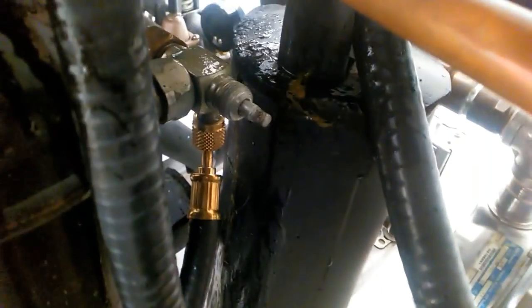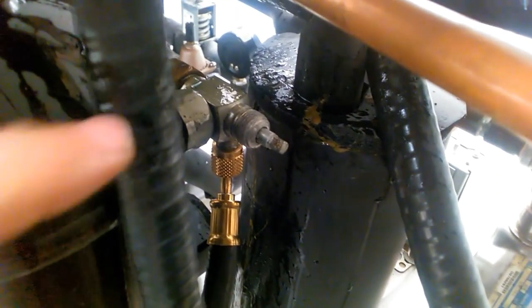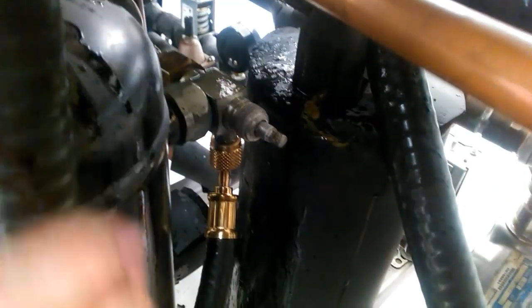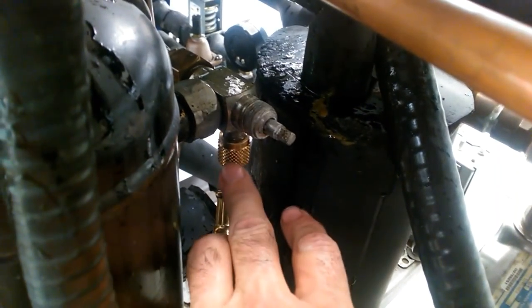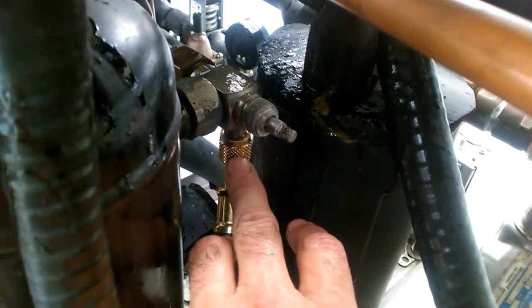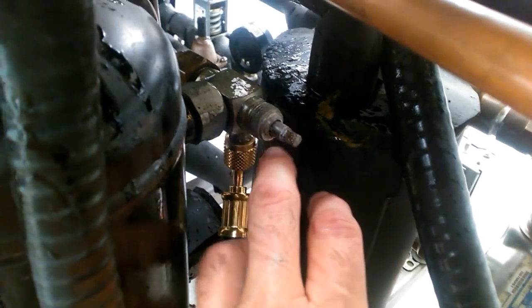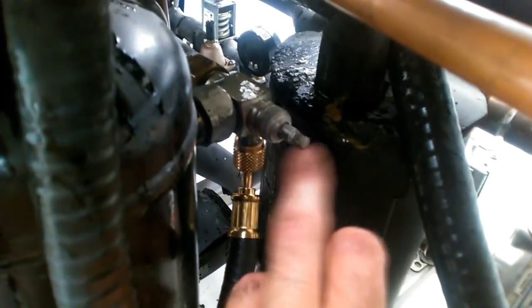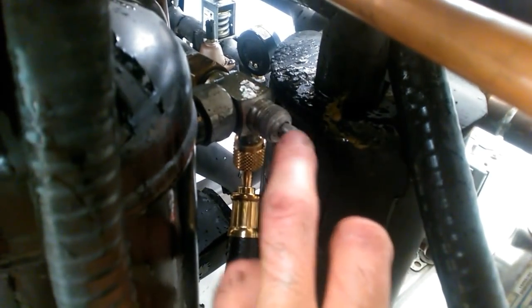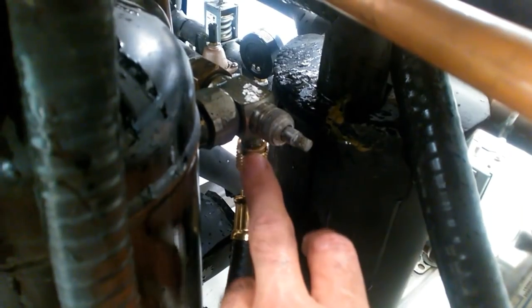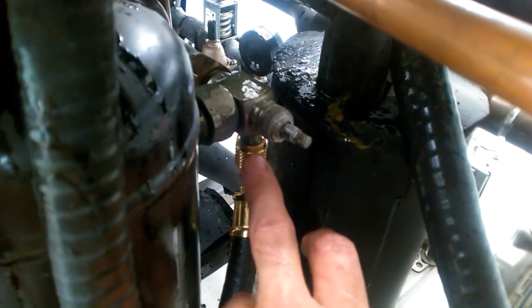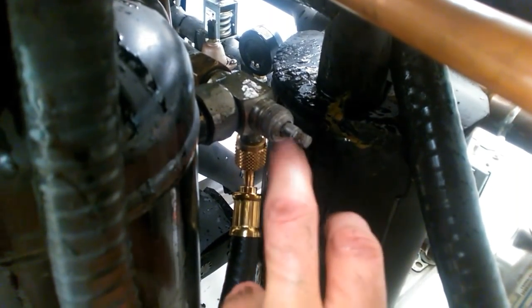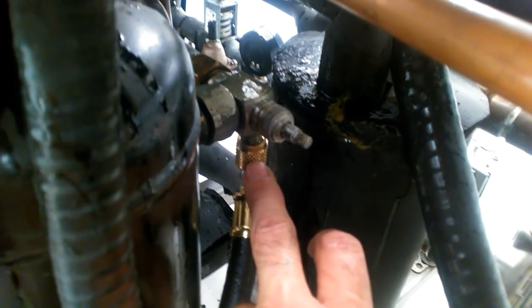Our next connection point is at the receiver outlet and the king valve. We don't have a Schrader there. That's fully open and we have a valve stem there. We crack that valve stem, get it about halfway and we're going to open that up. We don't have a Schrader there, so we're good. We don't need a core removal tool.